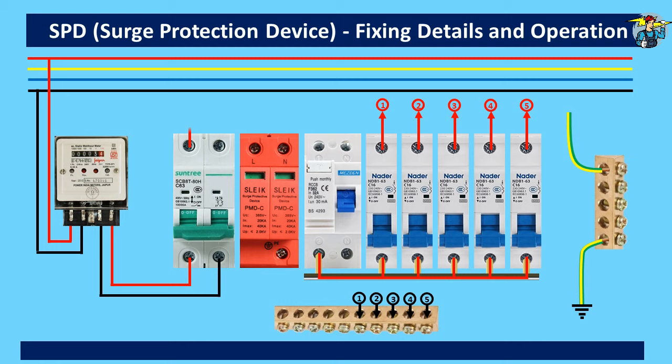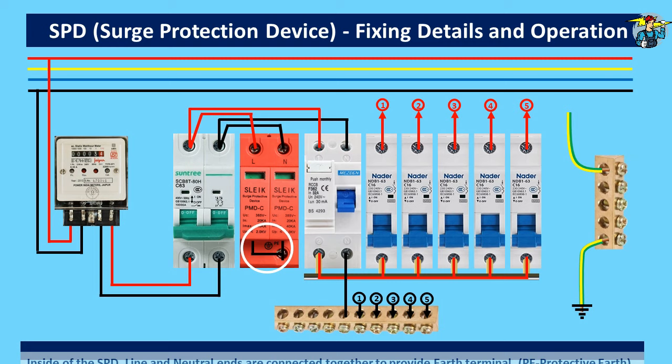The SPD phase and neutral terminals are to be connected to the top of the RCD, marked as L and N. You will see this SPD is actually connected parallel to the MCB. Even if we connect the SPD in an alternative method like this, it is okay. The requirement is to get it connected after the main switch to make sure it can be isolated for any repair work. At the bottom of the SPD you will see protective earth is marked, and you need to know that this point is made after joining the two line ends of SPD together from inside.